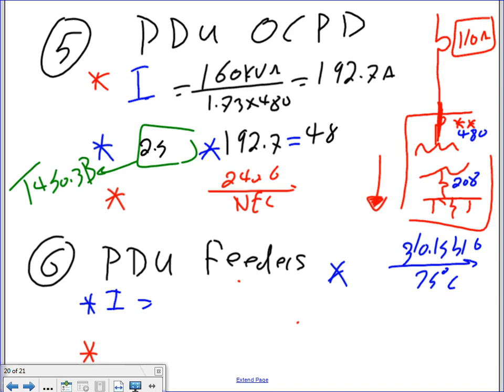481.8. Do I have a second? 481.8 amps. Take it to 240.6, and you see that will get you down to... We don't have 450, do we? We have to go to 400. Do we have 450? I can't remember. I don't think... Do we? Yeah, we have 450. So we're going to go down to 450. 450, yeah.